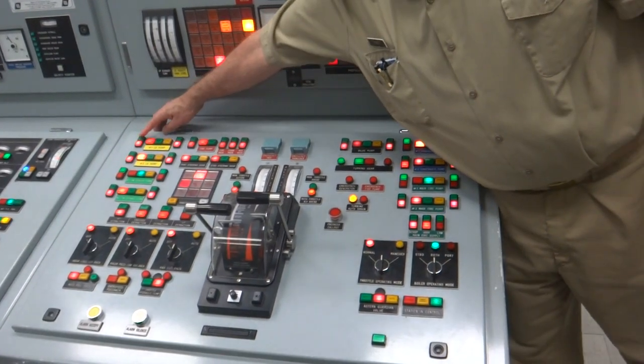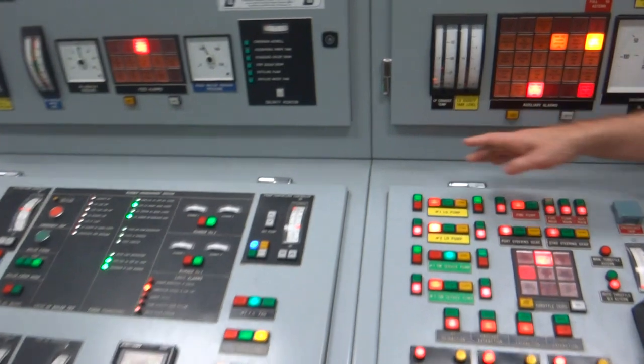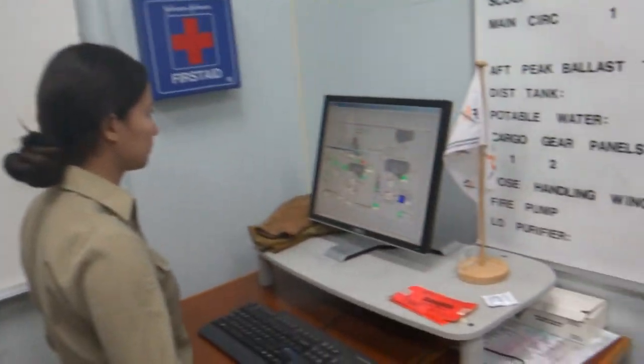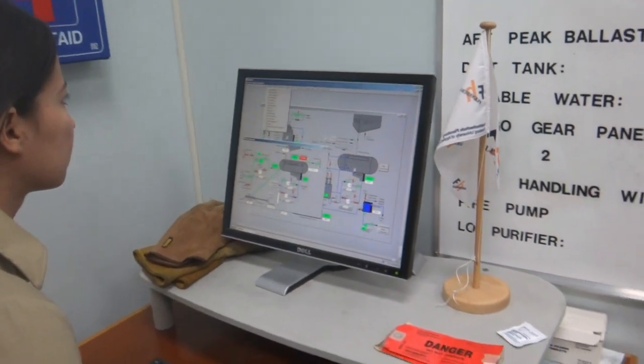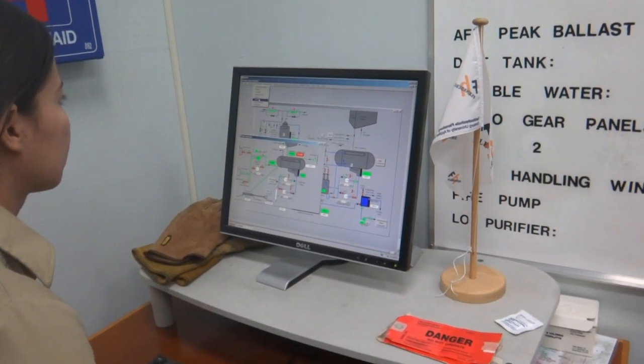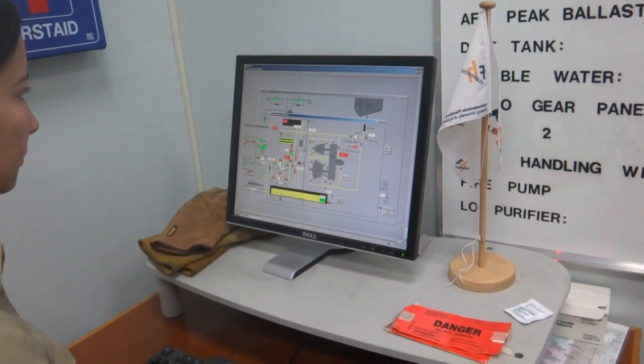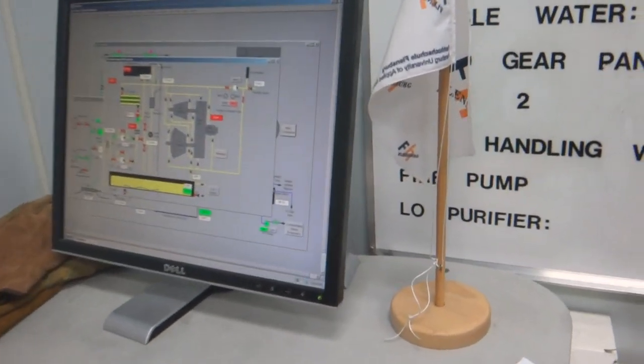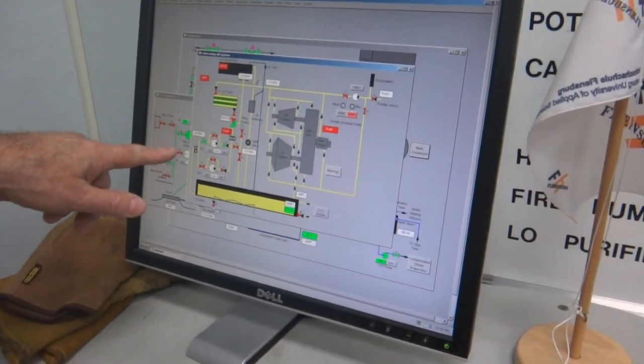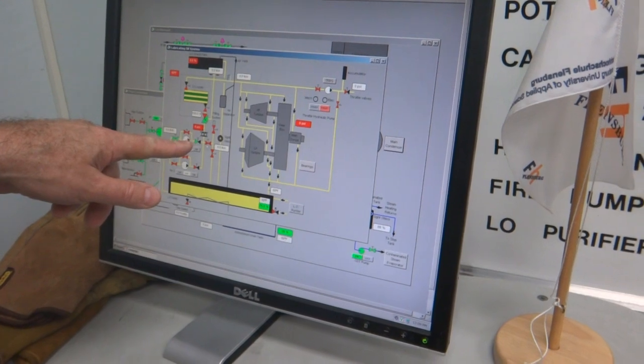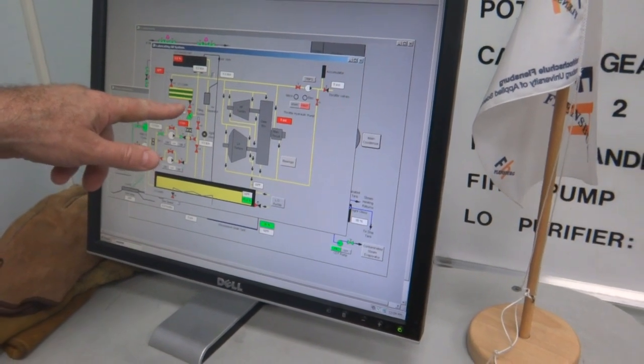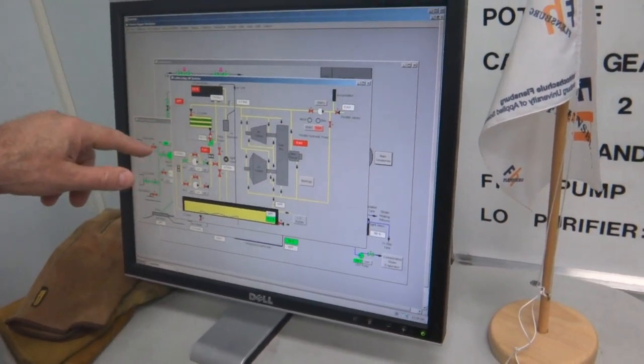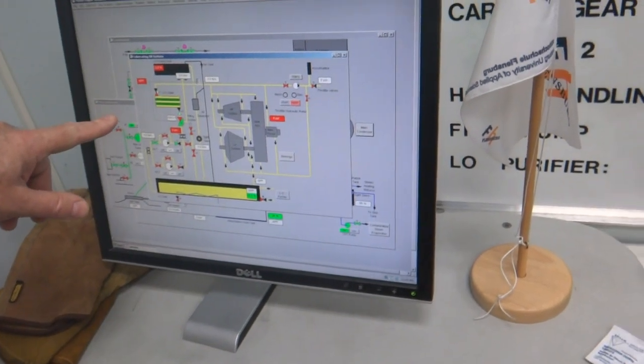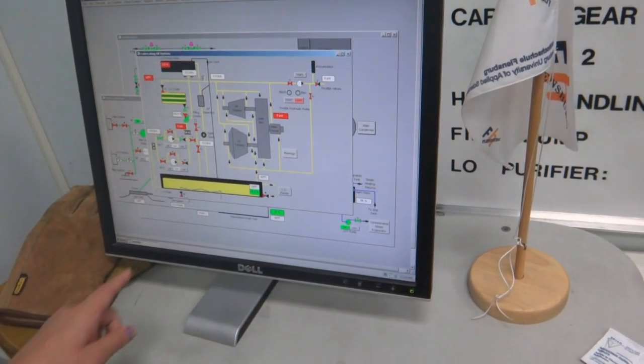So number 1, lube oil pump. Let's open up the suction, the discharge. Let's pull up the lube oil. It's on auxiliary systems, lube oil. And now, it's kind of a mess, but you've got suction through the suction strainer, discharge, suction valves are open, discharge strainer. Let's line up the cooler, just so it's available. And now go ahead and start number 1.